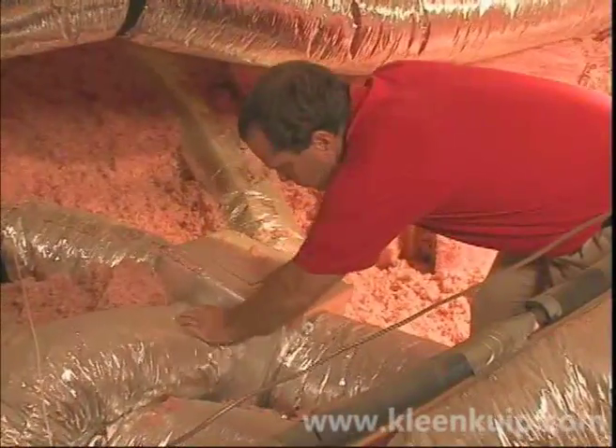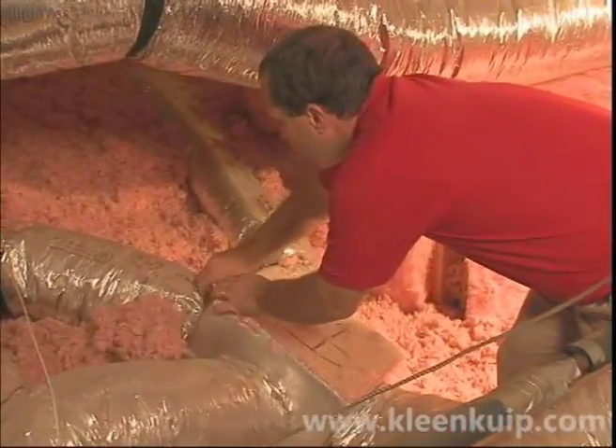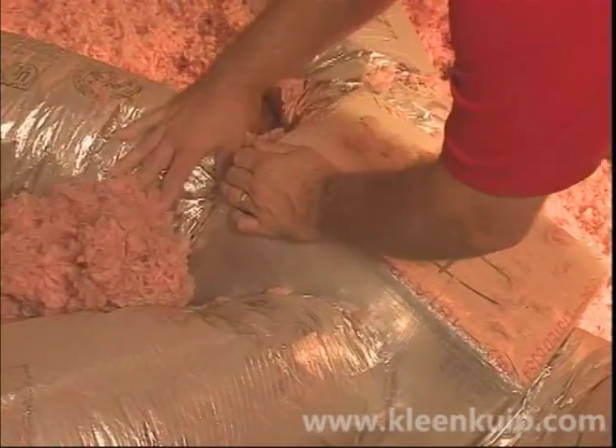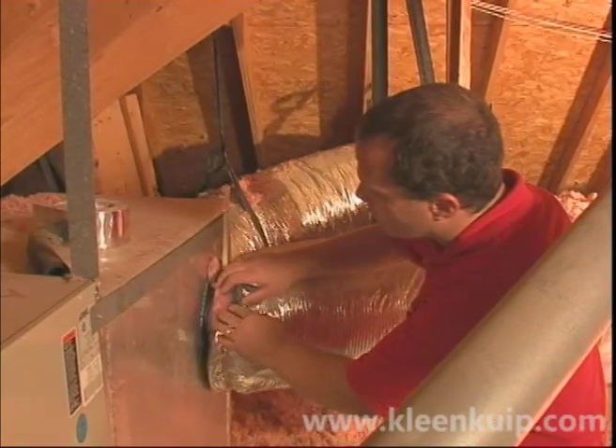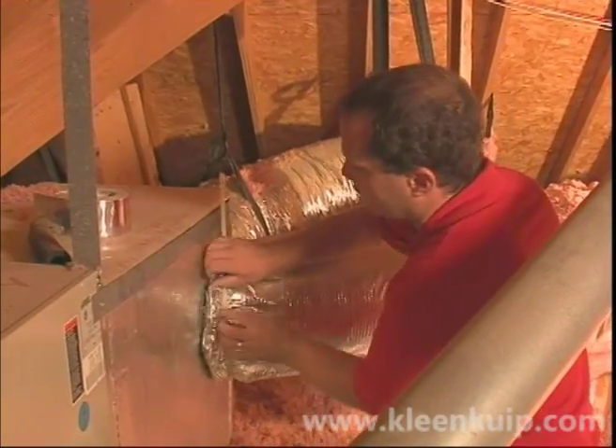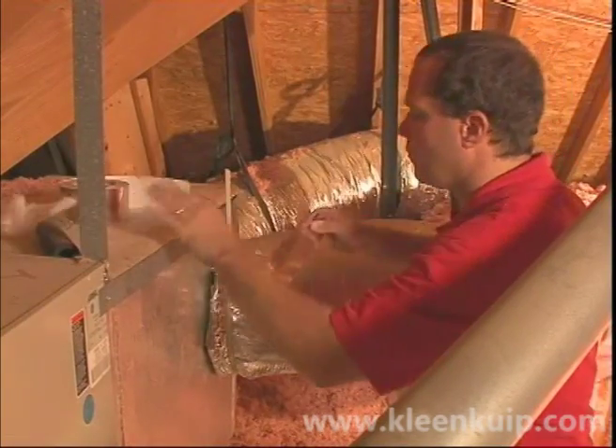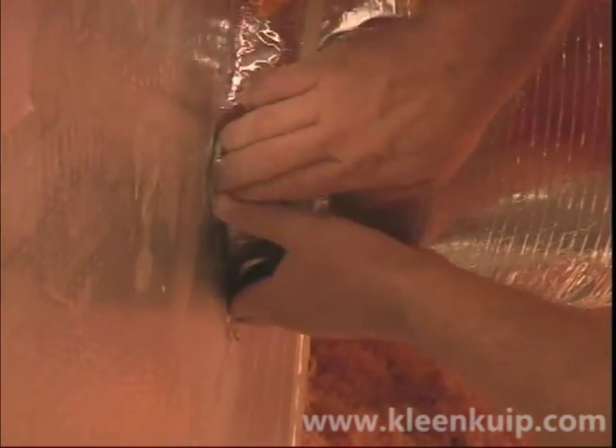While at the air handler, this is a great opportunity for you to inspect the ductwork throughout the system and look for any cracks and/or tears and/or ducts that are pulled away from the registers. Any mild or minor repairs can be accomplished with aluminum foil tape. Aluminum foil tape is easy to use and apply. And if this improves the efficiency of the air handling unit, this would be a service that most homeowners would be happy to pay for.